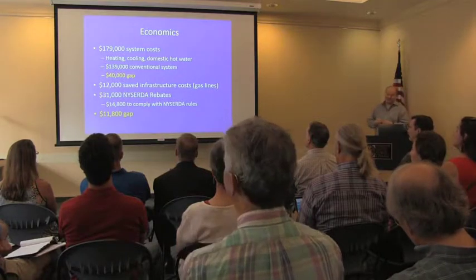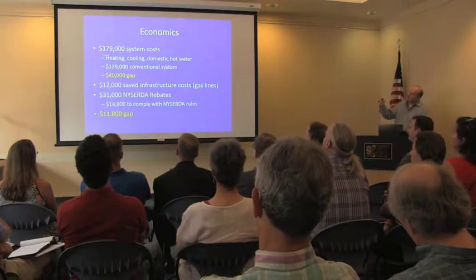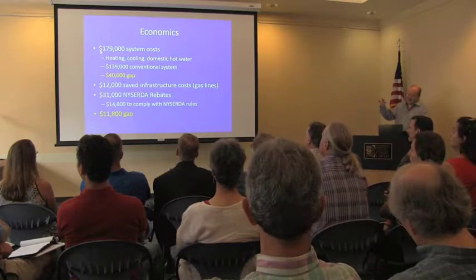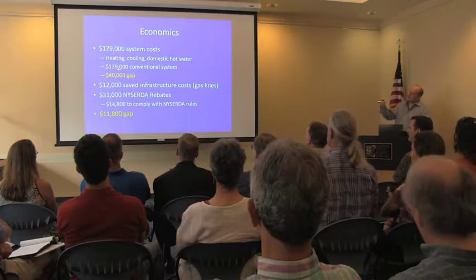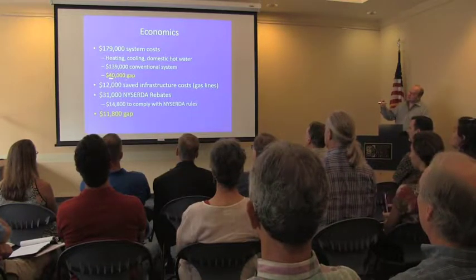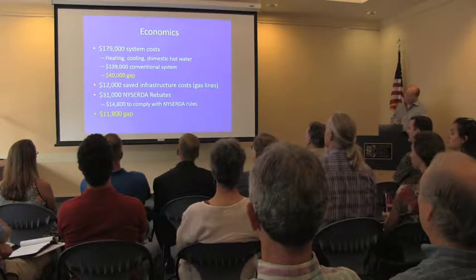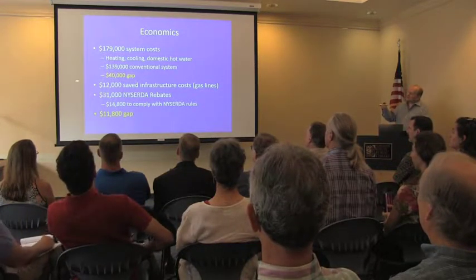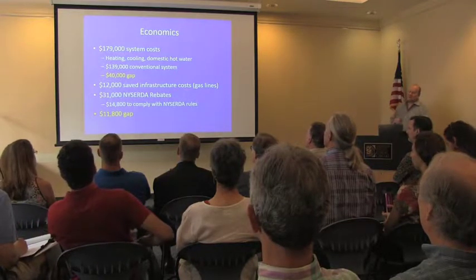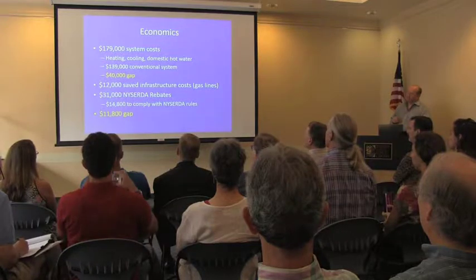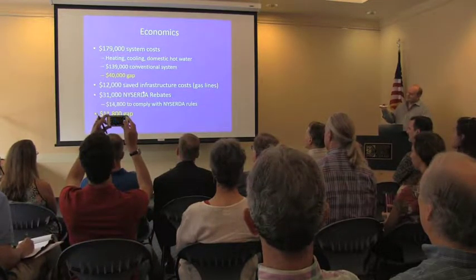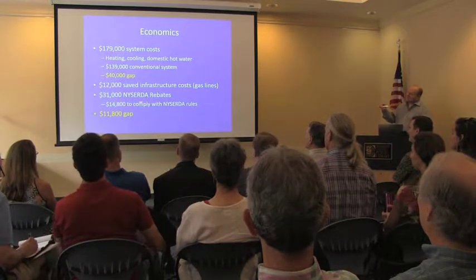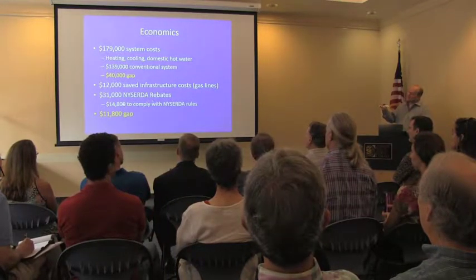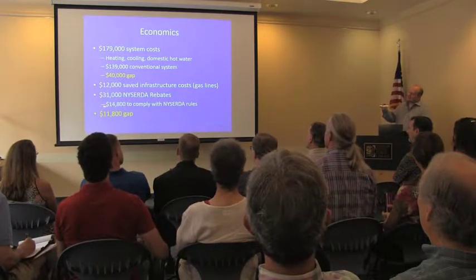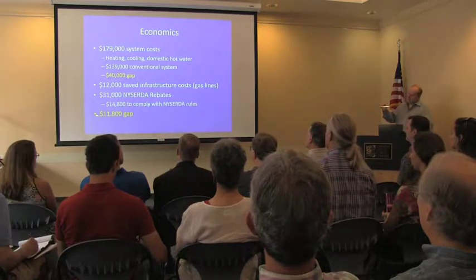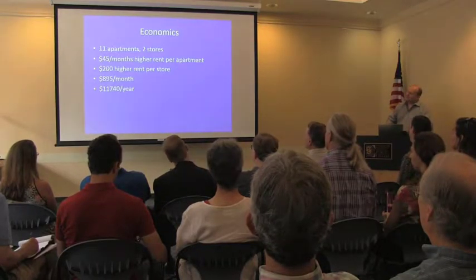Here were the economics for that building, just to show you how geo can work. The system costs were about $180,000, and the cheapest conventional system they had a bid on was about $140,000. So it was $40,000 more expensive. But they also saved $12,000 in gas lines for the building on the infrastructure costs there. There were some NYSERDA rebates applied too, but the NYSERDA rules are very strict about efficiency and complying with certain rules, so the system was slightly more expensive because of that. So there was still about a $12,000 gap in total.